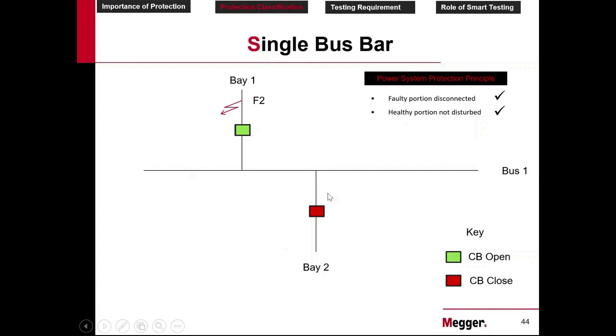There may be several other lines connected to it. So in this example, we have considered only a few. In reality, it is not going to be like this. Several lines will be connected to this bus and several outgoing lines will be connected to this bus. And when a fault occurs here, only this will be disconnected. So the other lines will continue to feed either in forward or in reverse direction.